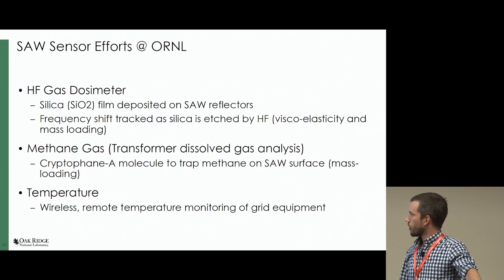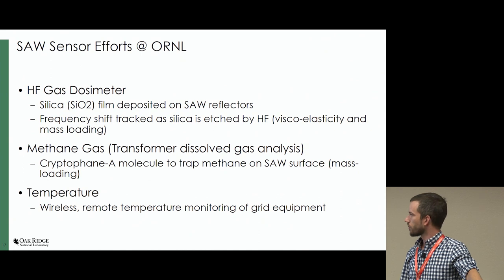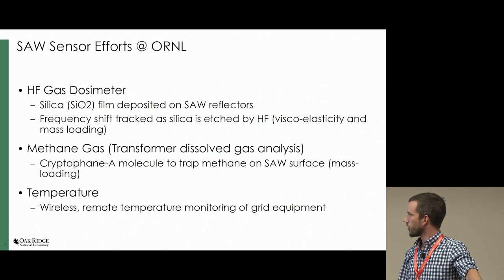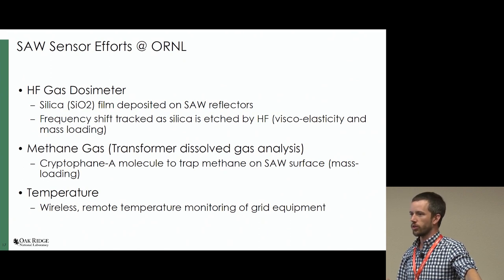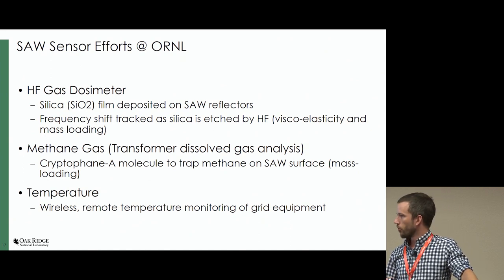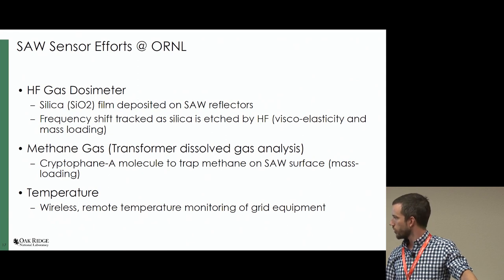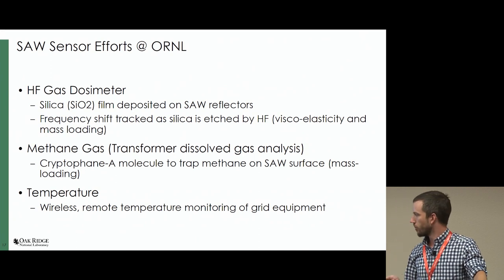Some of the sensors we're working on: HF gas detection — hydrogen fluoride gas — using silica deposited on the reflectors and tracking a mass loading shift and viscoelasticity. Methane gas detection, which would go in a transformer for power grid applications where they want to see off-gassing in the oils as a way to determine age or failure modes. And then temperature — just remotely measuring temperature.